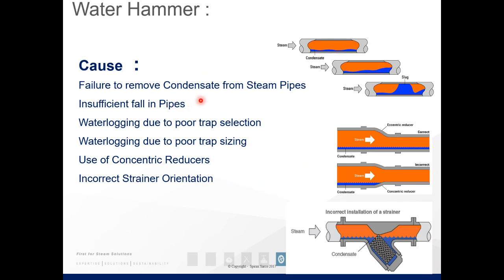Insufficient fall in pipes. A steam system should have a 1 in 100 drop. So for every 100 meters your main line travels, it should drop by 1 meter. Of course, at some point you're going to need to raise that pipe, so you will have a riser, and on that riser you should have a steam trap to be able to remove the condensate that builds up at that low point. Waterlogging due to poor trap selection. Again, we covered that before. If the trap is undersized or the wrong type of trap, it's not going to remove the condensate.